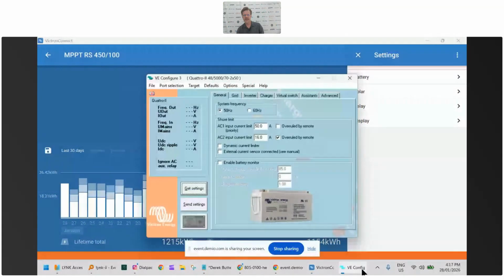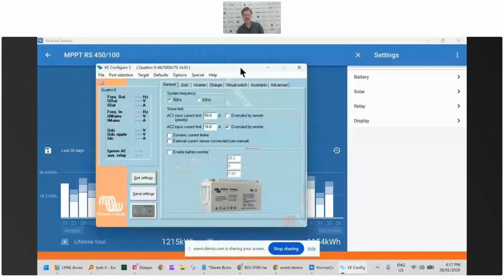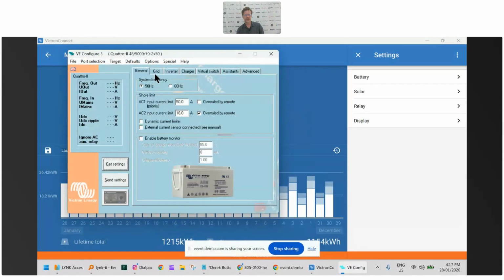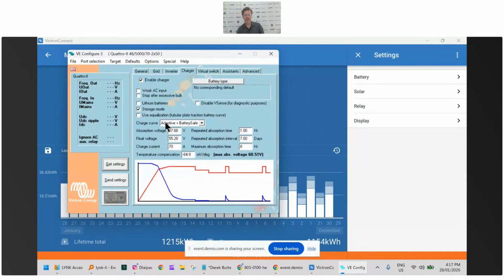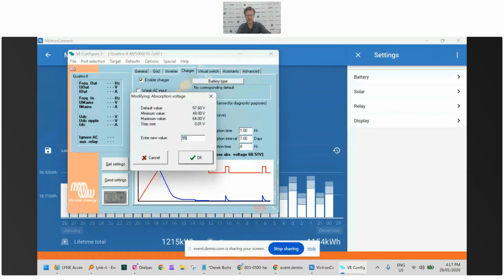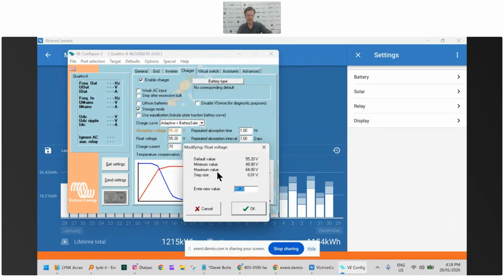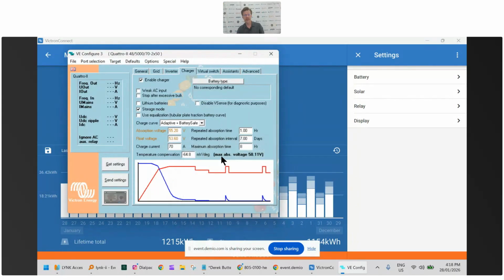And then we have the same in VE configure. So in VE configure, what we're mostly interested in is our charge voltages here. So we're going to set those to 55.2 and 53.6.